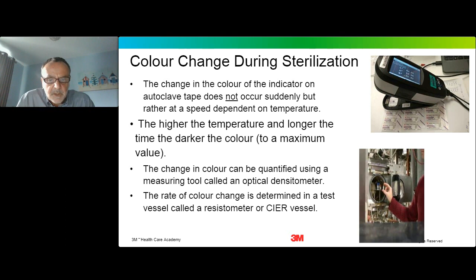And this is effectively a very small autoclave. It has a chamber capacity of about 20 litres. You can see this resistometer in the picture here. And the reason why it's small is so that you can control the conditions within the chamber very carefully. And you get a very rapid rise in temperature when steam is admitted. And similarly, at the end of the exposure phase, you get a very dramatic decrease in temperature. So you're effectively using what's called a square wave heating profile in that chamber. And that means you can establish very accurately the colour change characteristics of the autoclave tape.